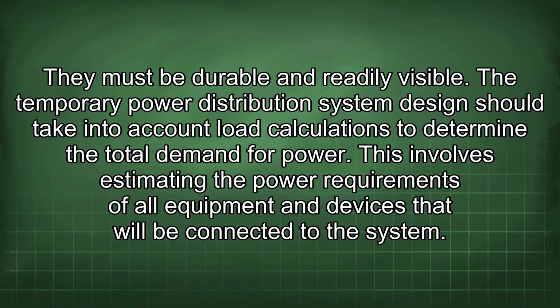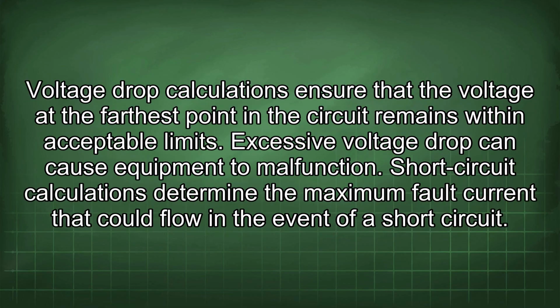A temporary power distribution system design should take into account load calculations to determine the total demand for power. This involves estimating the power requirements of all equipment and devices that will be connected to the system. Voltage drop calculations ensure that the voltage at the farthest point in the circuit remains within acceptable limits. Excessive voltage drop can cause equipment to malfunction. Short circuit calculations determine the maximum fault current that could flow in the event of a short circuit.